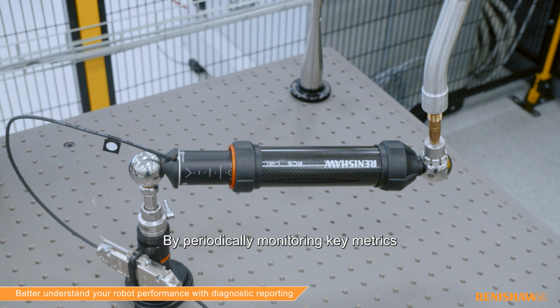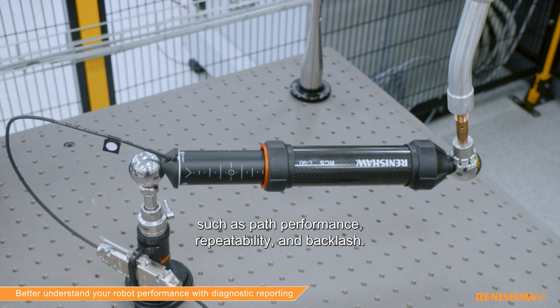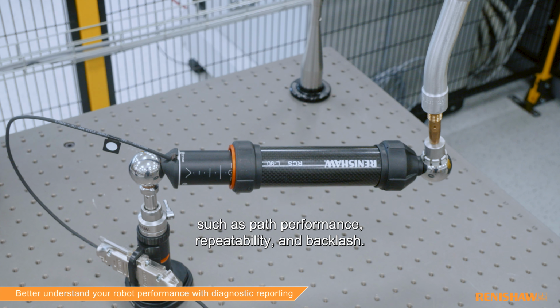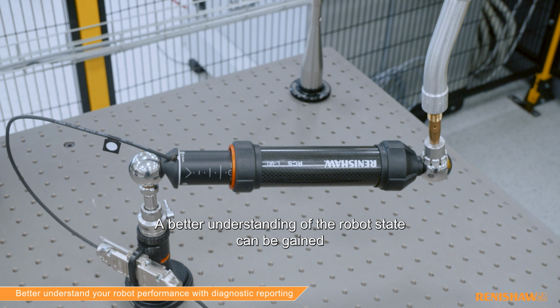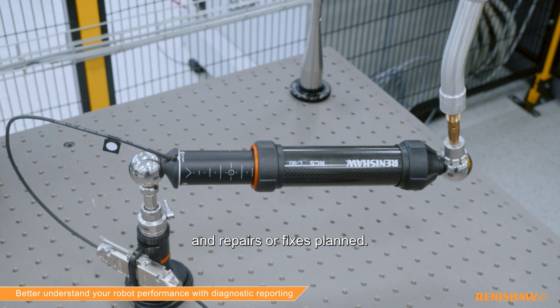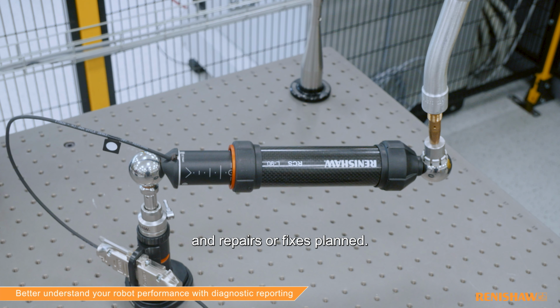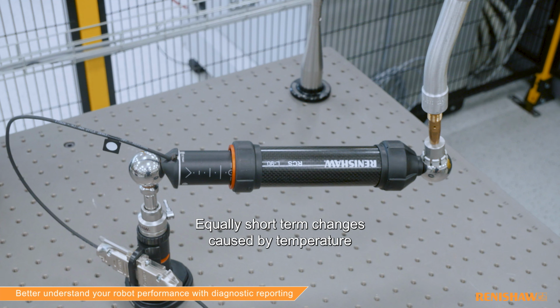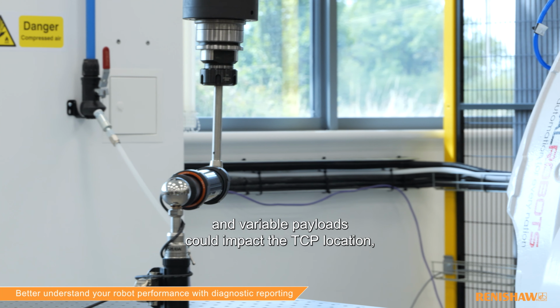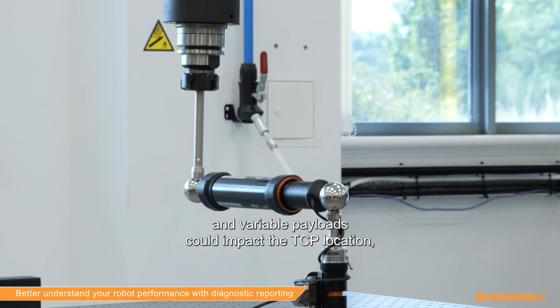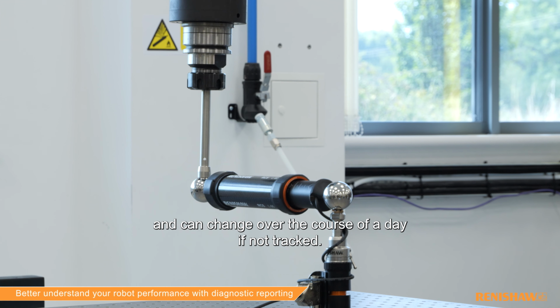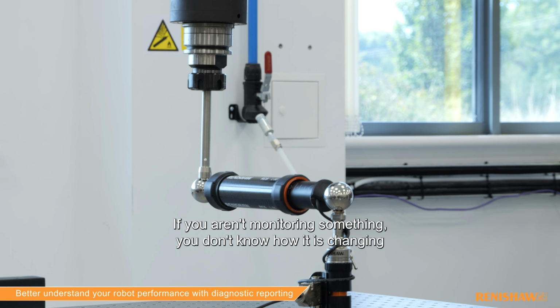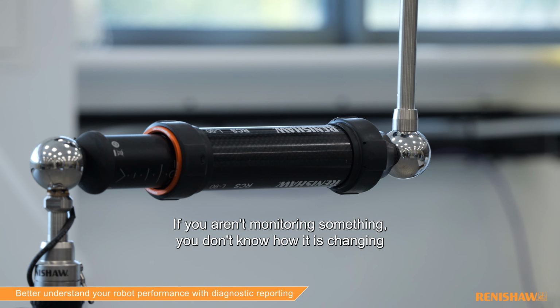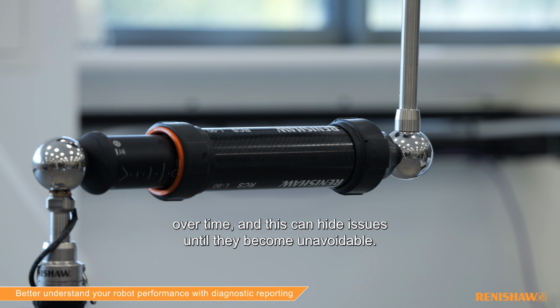By periodically monitoring key metrics such as path performance, repeatability and backlash, a better understanding of the robot's state can be gained and repairs or fixes planned. Equally, short-term changes caused by temperature and variable payloads could impact the TCP location and can change over the course of a day if not tracked.